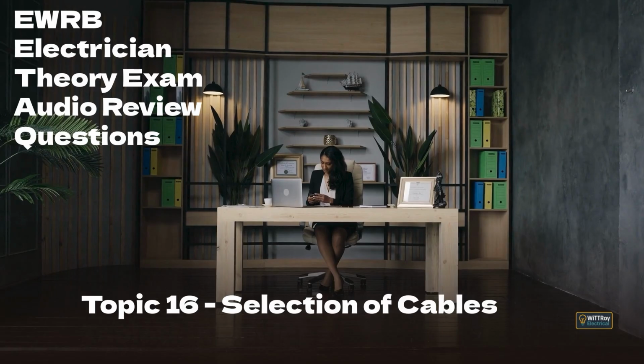If the voltage rating is too low, the insulation can be overstressed, leading to partial discharge, tracking, or breakdown, especially during surges.